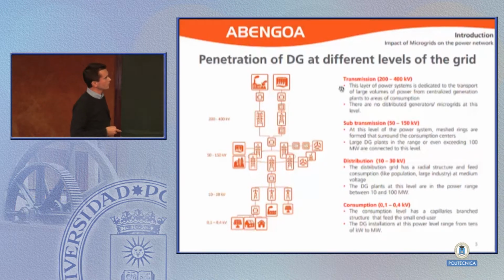To give an idea about the size of these power plants: in the sub-transmission grid, we have distributed generation plants in the range of or even exceeding 100 megawatts. In the distribution grid, where most industry and large population areas are fed with power, DG plants are at the level of 10 to 100 megawatts. At the consumption level, the last level of the power grid with low voltage consumers, DG installations are usually in the range of a few kilowatts to 1 megawatt.